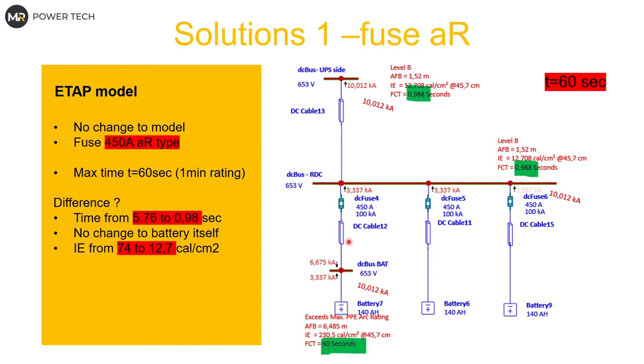So I looked for simple solutions. The first was to change the fuse type — not the size, just from gG to aR (rapid, fast-acting type). This already made a huge difference: tripping time went from almost 6 seconds down to 1 second. The main bus and other bus results improved dramatically — from 74 cal/cm² down to 12 cal/cm². A huge improvement already.